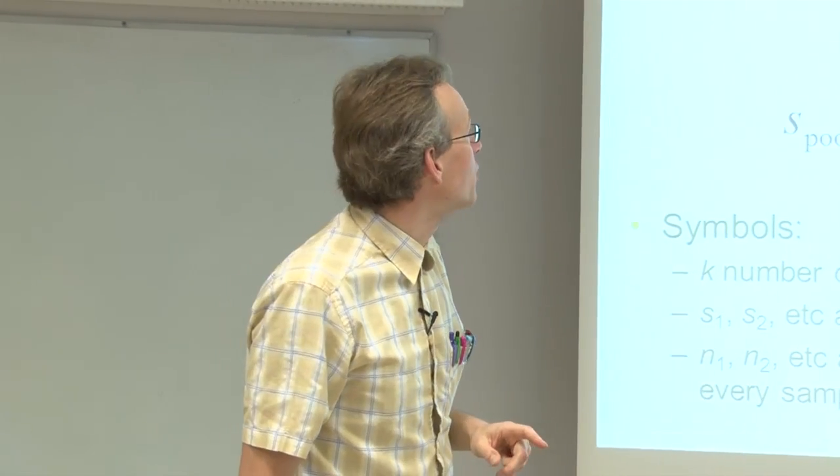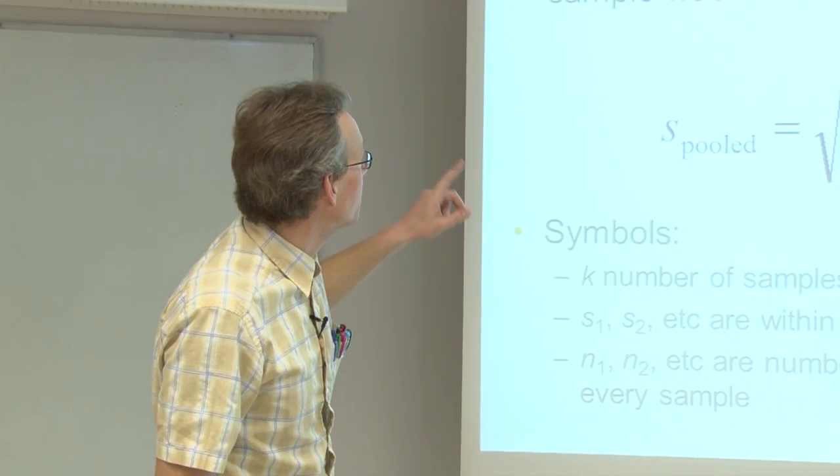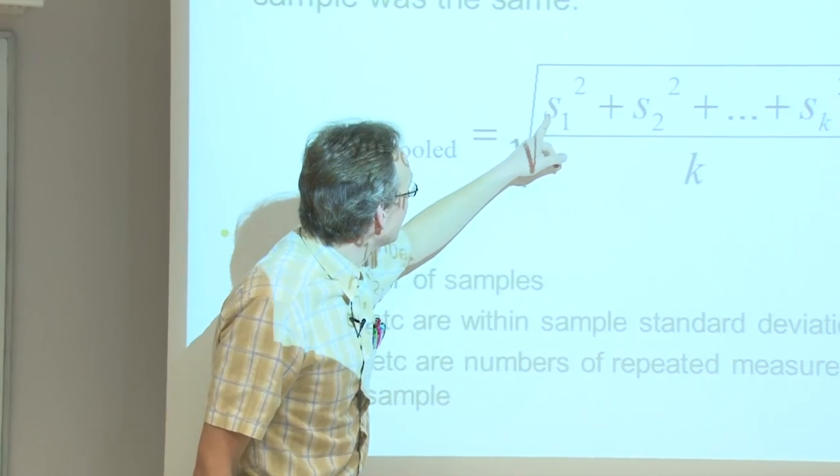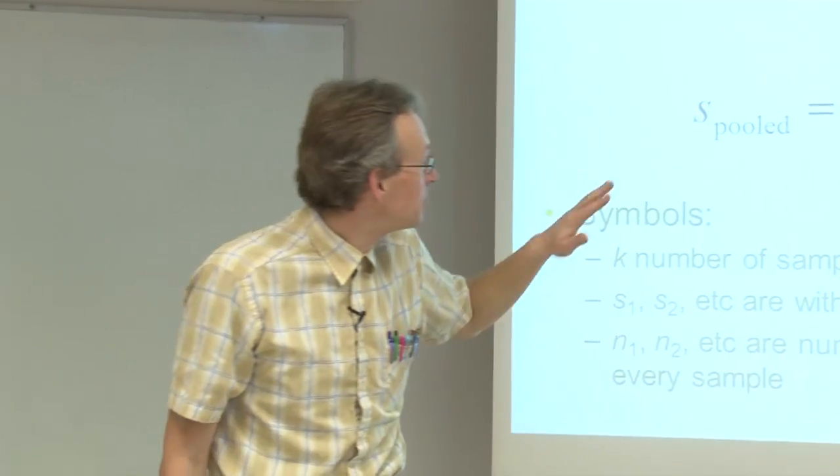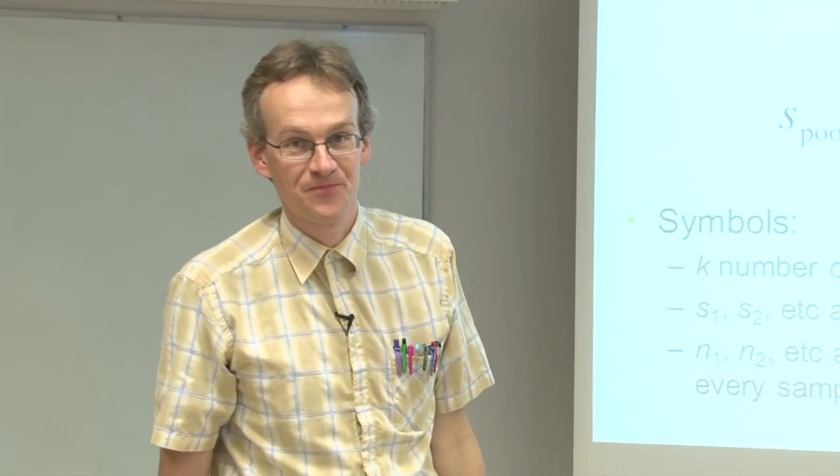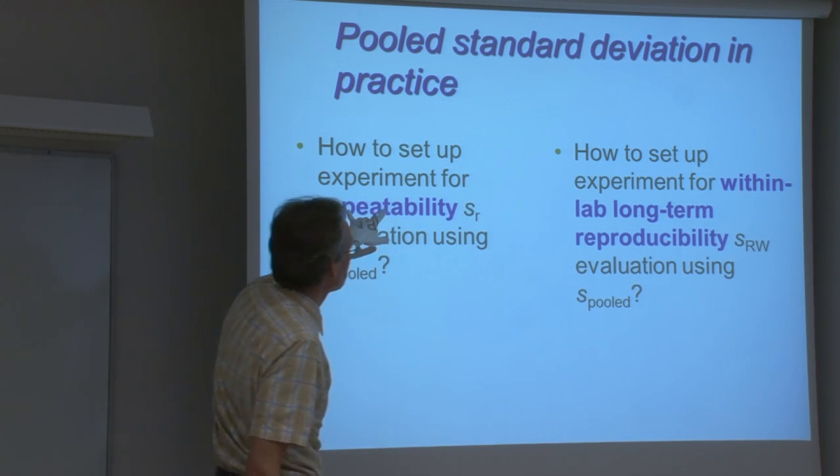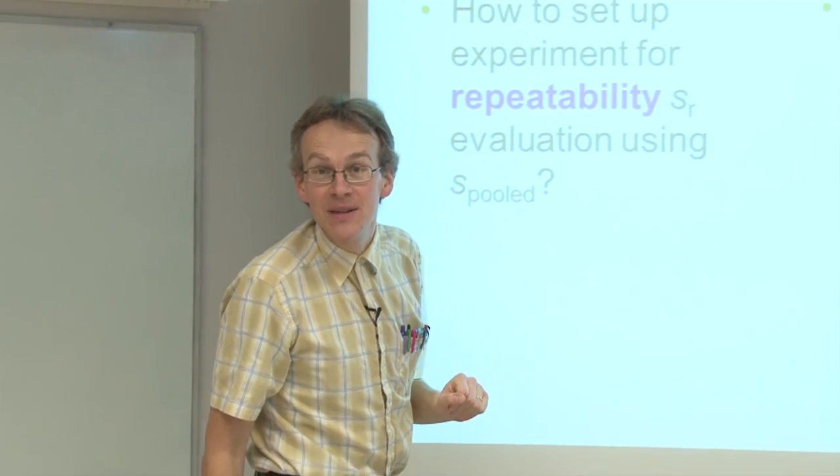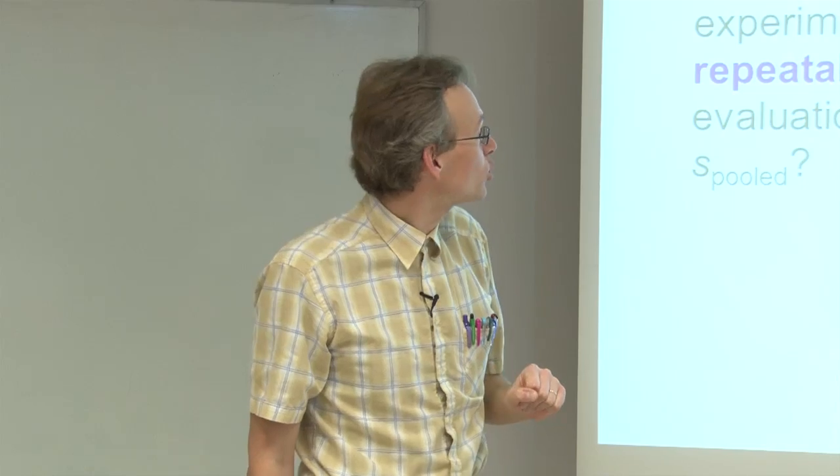If, however, the measurement was organized in such a way that the number of measurement with each of the samples was the same, then the formula becomes simpler, and the numbers of measurements can be omitted altogether. I mentioned that both repeatability and within-lab long-term reproducibility can be evaluated with pooled standard deviation, and let us see now how to set such experiments up in practice.